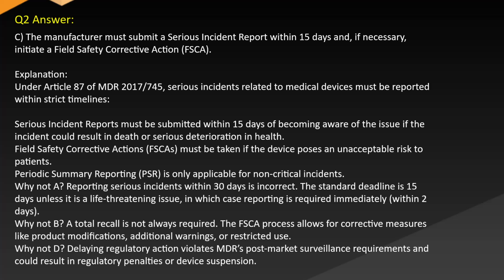Why not A? Reporting serious incidents within 30 days is incorrect. The standard deadline is 15 days, unless it is a life-threatening issue, in which case reporting is required immediately, within 2 days. Why not B? A total recall is not always required. The FSCA process allows for corrective measures like product modifications, additional warnings, or restricted use. Why not D? Delaying regulatory action violates MDR's post-market surveillance requirements and could result in regulatory penalties or device suspension.